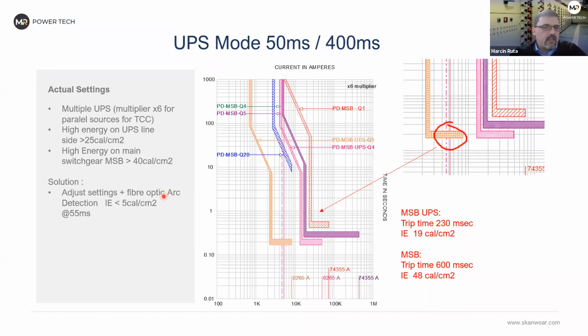So we can improve it by fiber optic arc detection because of the selectivity challenge here. We can also adjust the settings a bit, but it won't be a big difference. Also, the line side of this UPS breaker was slightly higher because of the 400 milliseconds and was, I think, 25, 26 calories in this specific example.